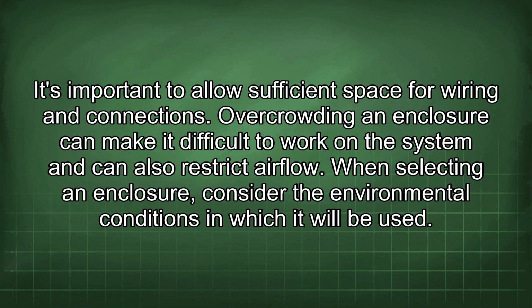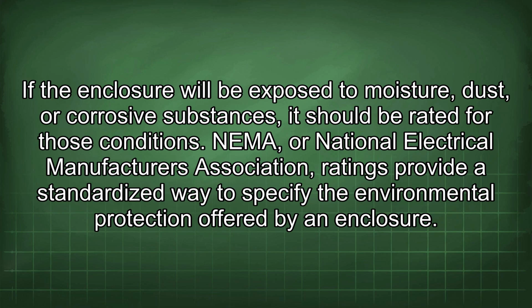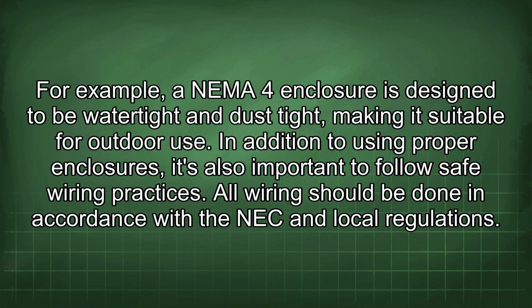When selecting an enclosure, consider the environmental conditions in which it will be used. If the enclosure will be exposed to moisture, dust, or corrosive substances, it should be rated for those conditions. NEMA, or National Electrical Manufacturers Association, ratings provide a standardized way to specify the environmental protection offered by an enclosure. For example, a NEMA 4 enclosure is designed to be watertight and dust-tight, making it suitable for outdoor use.